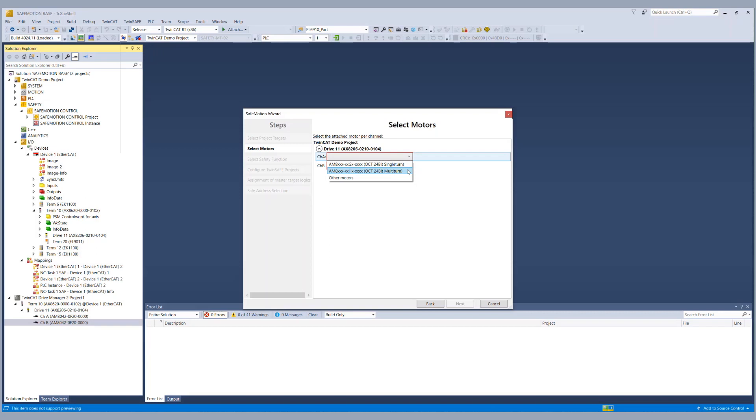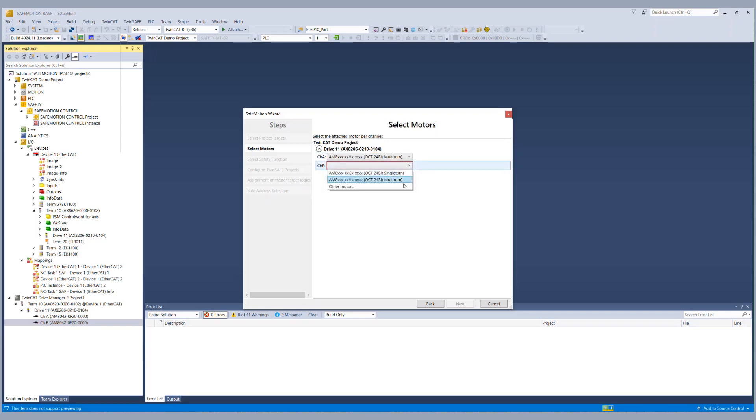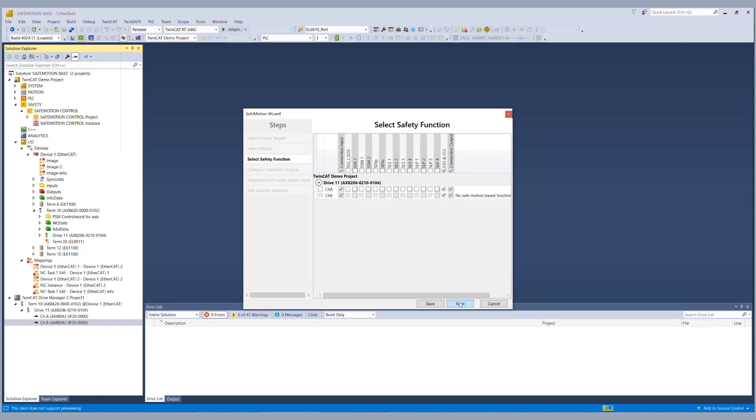In the case of an EnDat 2.2 safety encoder we would have to choose other motors because it's not an OCT safety encoder of course but in order to realize a safe limited speed functionality for the EnDat 2 encoder in the current version of the TwinSafe motion wizard we choose OCT multi turn as feedback for channel A and other motors for channel B. Today we want to realize an SLS functionality for channel A so we choose SLS for channel A.